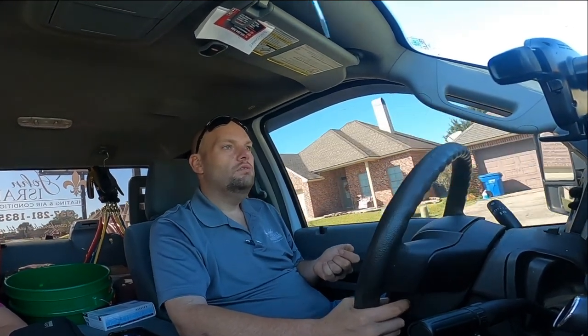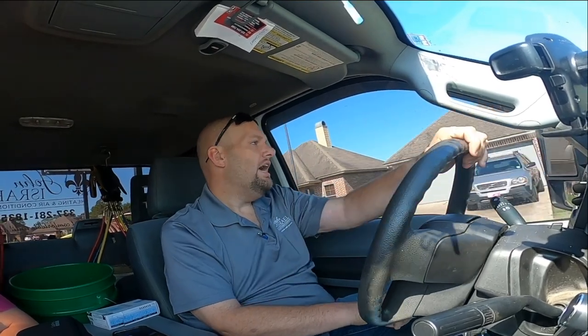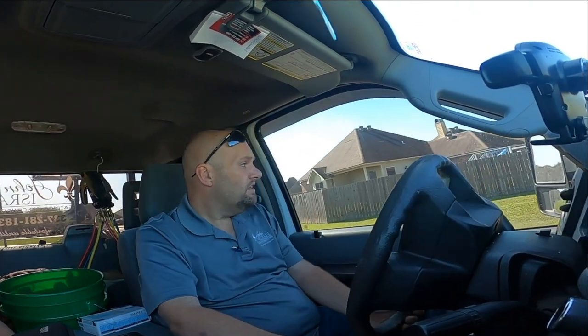He had 5 kW worth of heat running with the air. Rather than fix the issue, he chose to just disconnect that particular heat strip and come back at a later date to fix the problem, because I gave him a quote to change out the sequencers. It's a mobile home. I gave him a quote to change out the sequencer that was stuck, and some of the wires were charring, burning. Replace those. He didn't want to do it right then and there, so we unplugged the heat strip that was running to get the air running.